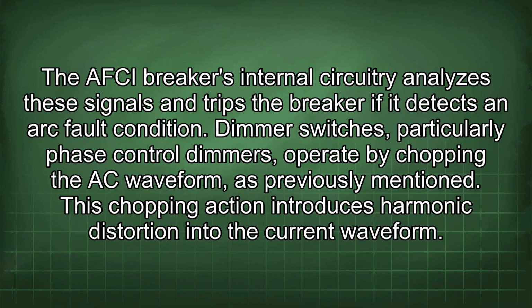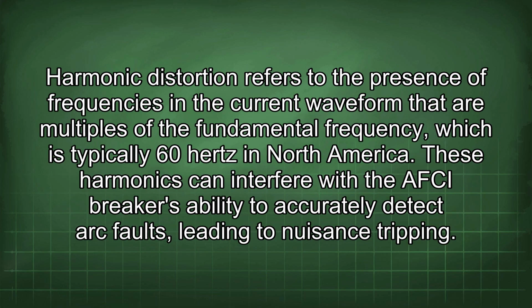Dimmer switches, particularly phase-controlled dimmers, operate by chopping the AC waveform, as previously mentioned. This chopping action introduces harmonic distortion into the current waveform. Harmonic distortion refers to the presence of frequencies in the current waveform that are multiples of the fundamental frequency, which is typically 60 Hz in North America. These harmonics can interfere with the AFCI breaker's ability to accurately detect arc faults, leading to nuisance tripping.